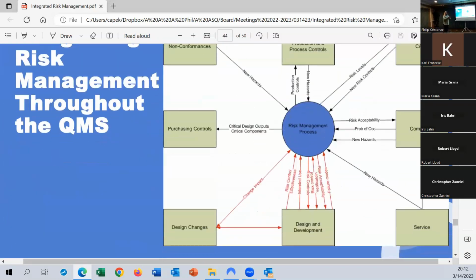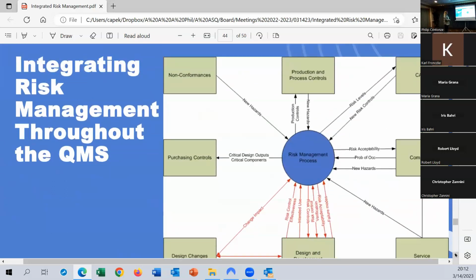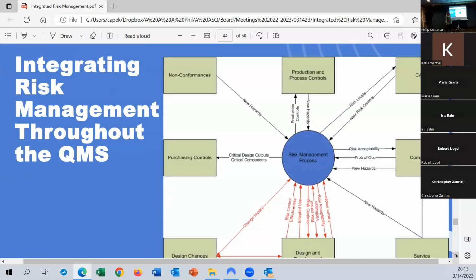Now, risk management is something that we do and is considered part of design, but it really informs or passes information on to everything else. So non-conformances, we can identify new hazards from non-conformance. Purchasing controls, we might have identified CQAs, or critical design outputs, critical components that we might have to impose some purchasing controls on. Design changes, we need to determine the impact of design changes and update our risk file if need be. Production and process control, we might identify new hazards through that, and we might need to impose new controls in production to reduce the likelihood of some hazards.